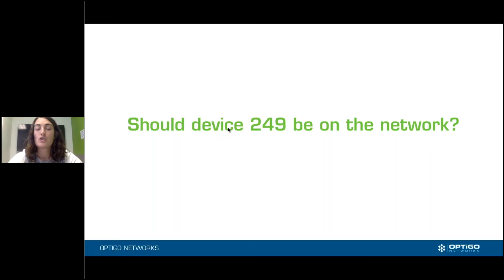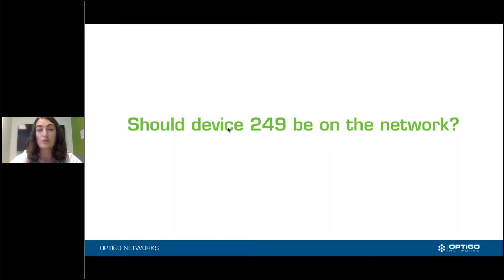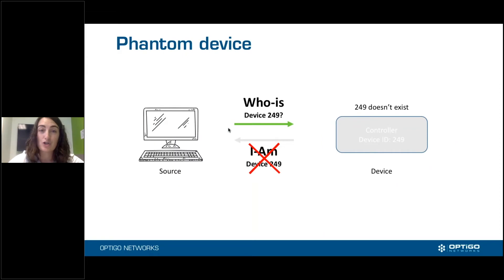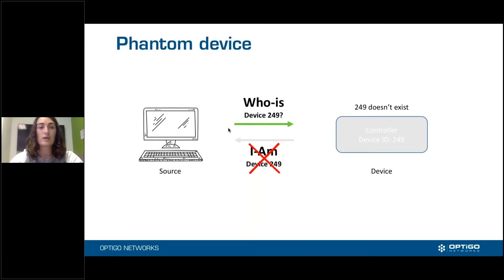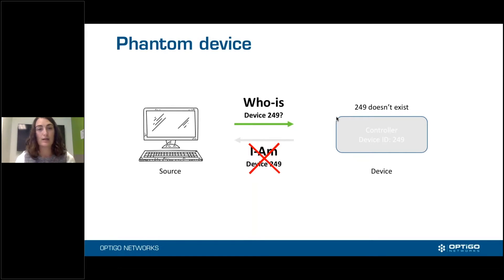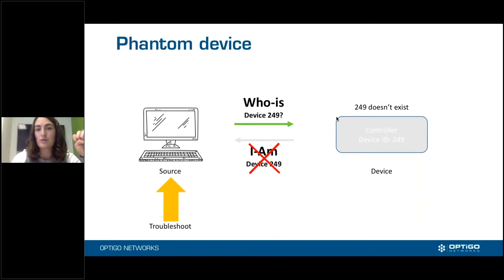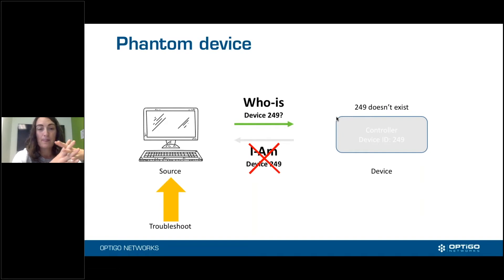If the device does fit within your numbering scheme, you hopefully have a device list, and you can check whether that device ID has actually been assigned. If the answer is no — this device should not be on the network — you have what we call a phantom device. The source device, our computer, is sending Who-Is device 249, but there is no device 249. It shouldn't exist, and the source device shouldn't be looking for it. In this case, the problem is the source device.